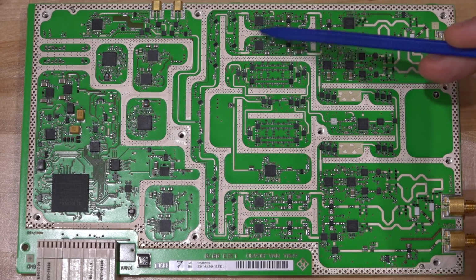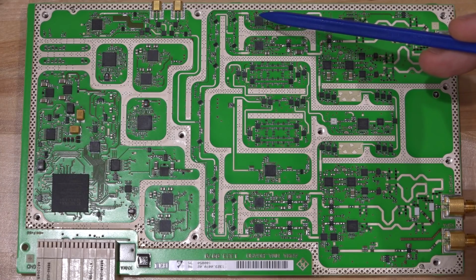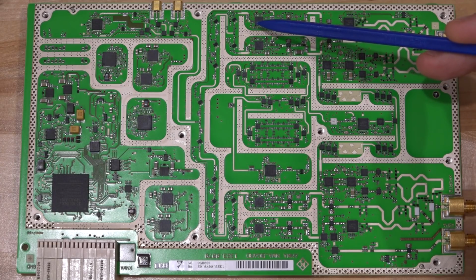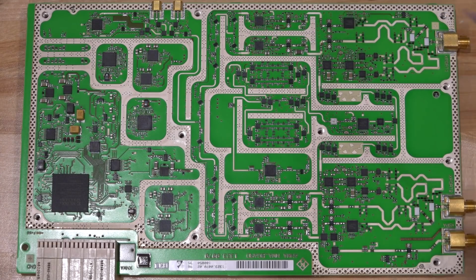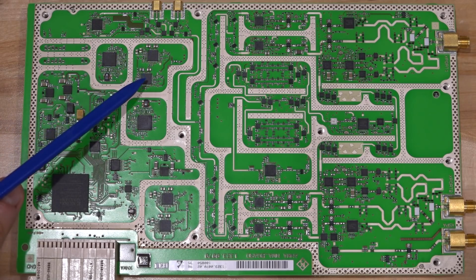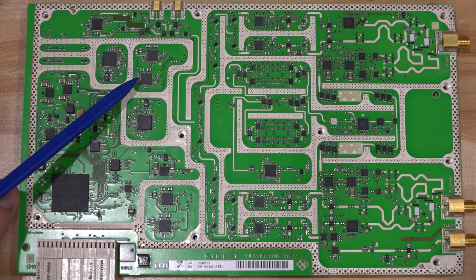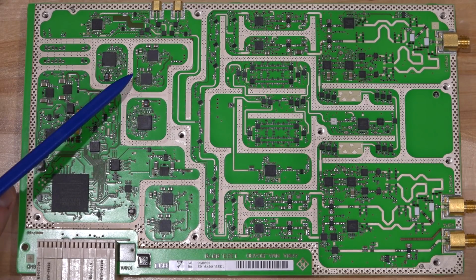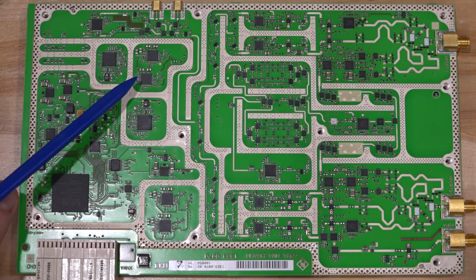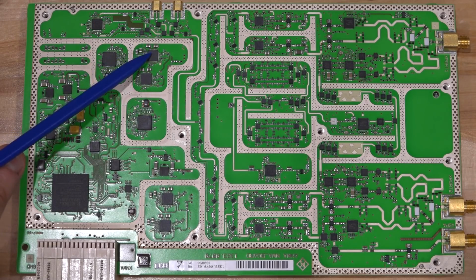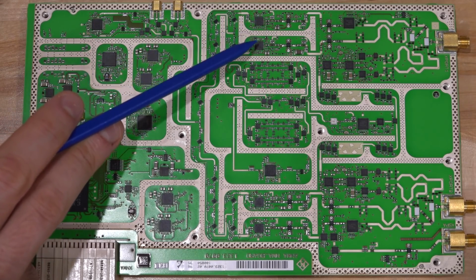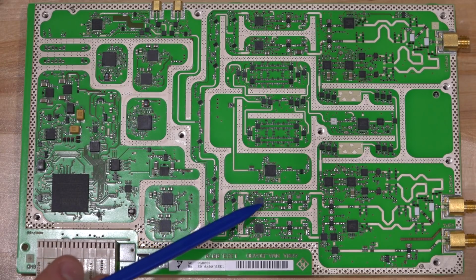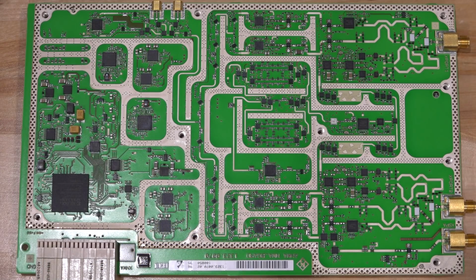So those differential IF outputs, I believe, go into a set of filters on the other side of the board. They appear to be all passive. And I think they make their way towards these two ADCs. These are 10 megasample per second, 16-bit ADCs. They only have a bandwidth of about a few megahertz. That's why I don't think this instrument can do the 40 megahertz analysis. And you can see that there's 2 of them here for these 2 mixers, 2 more over here for these 2 mixers. I believe that's where the connection is made.